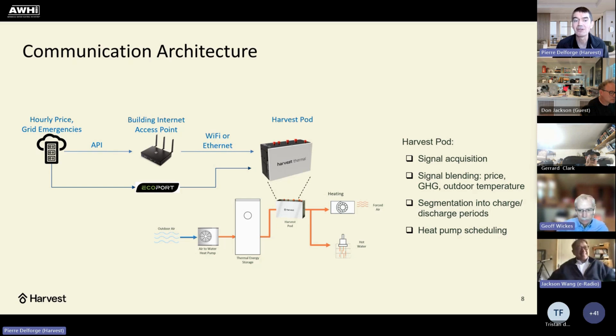After 24 hours, you start seeing patterns emerge. They're pretty rough for the first few days, and then over time they get better and better, and you're able to see differences between weekday and weekend, weather-related differences, how it correlates with temperature, wind, solar gains, and all this stuff. Each home behaves differently, particularly from a heating perspective — if there's a sunny day with a lot of west-facing glass, for example, it behaves differently. We don't know the energy model for the home, but we can see how the home responds to the weather. That's basically the internal algorithm within the Harvest Pod that monitors and uses that to build a demand forecast.